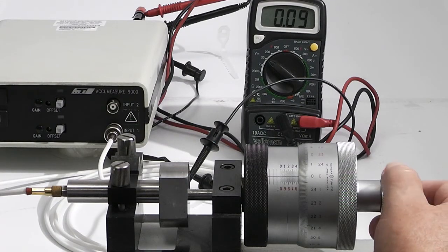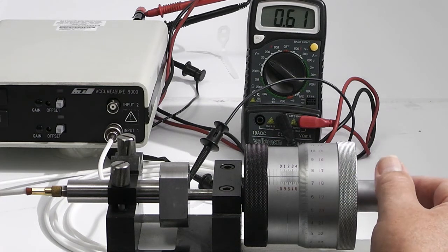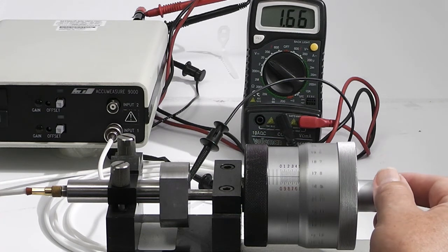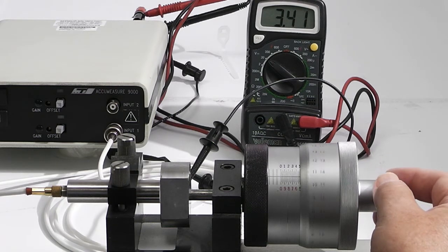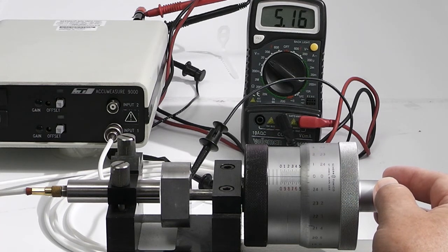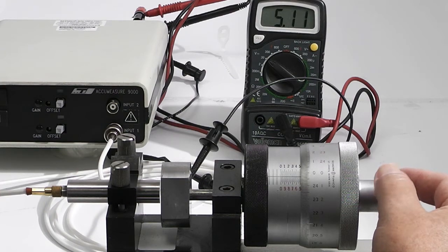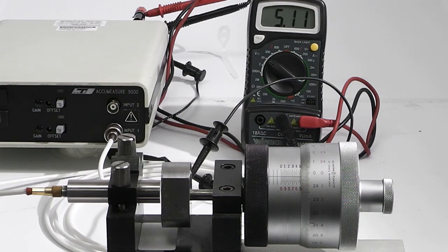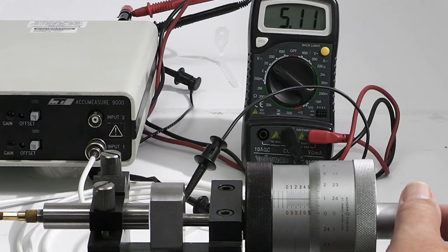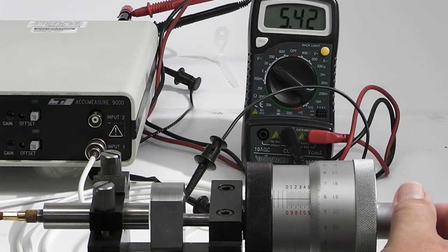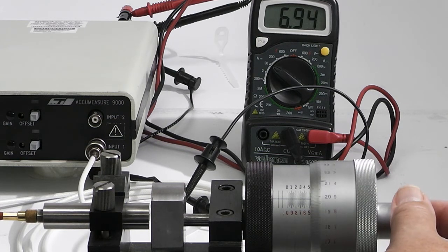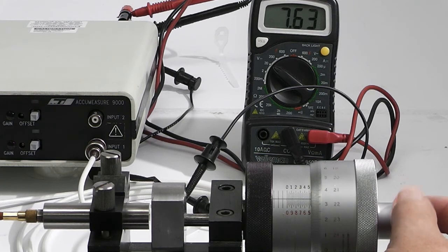The micrometer on the calibration fixture is adjusted counterclockwise to get to a gap of 1.25mm, which corresponds to half gap. At this point, the display should read close to 5 volts. The micrometer is further rotated counterclockwise to read 2.5mm or 100 mils of full gap. And the resultant voltage should be pretty close to 10.0 volts.